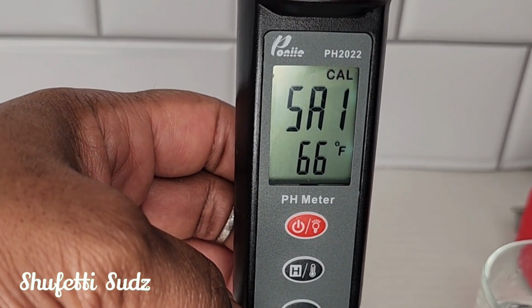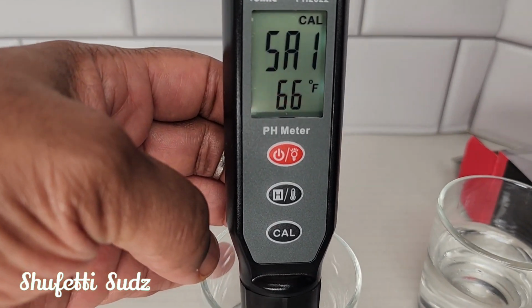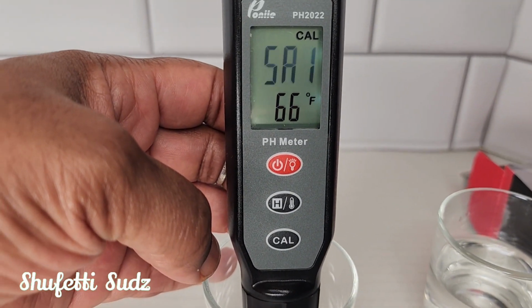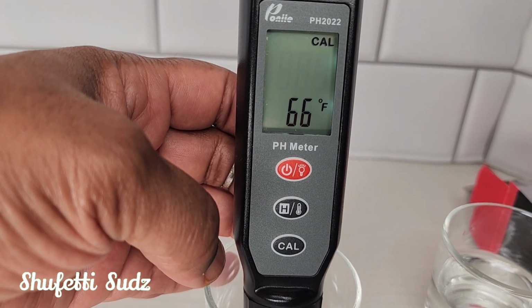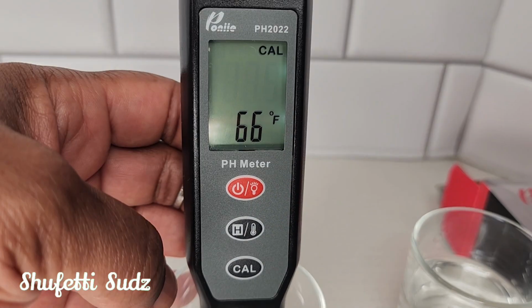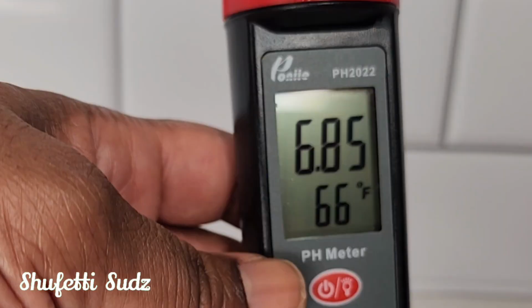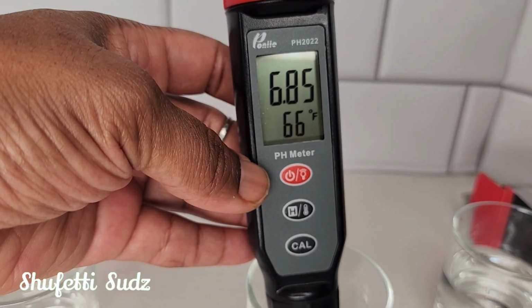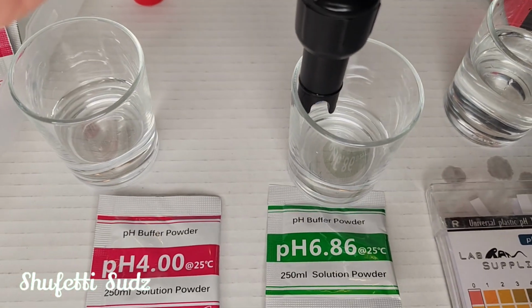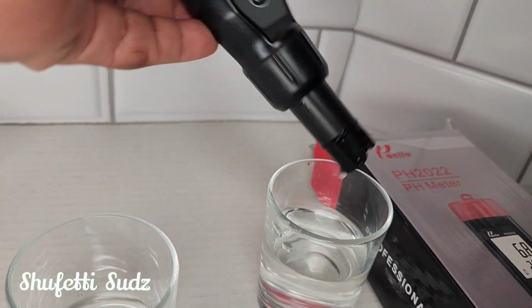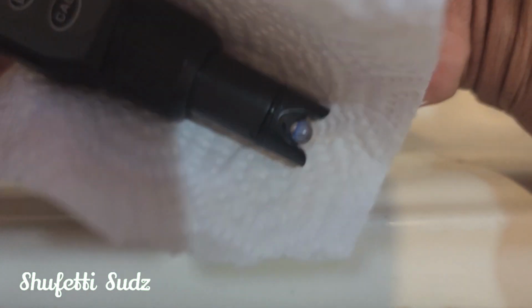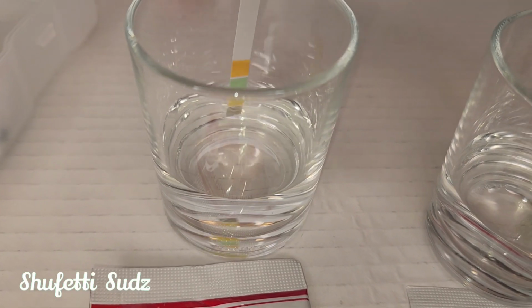Put the sensor into the pH 6.86 solution, submerge completely. Press the CAL button and wait for the ADC value to stabilize. Remove the sensor from the solution, clean the bulb with distilled water, and wipe with a clean tissue paper.